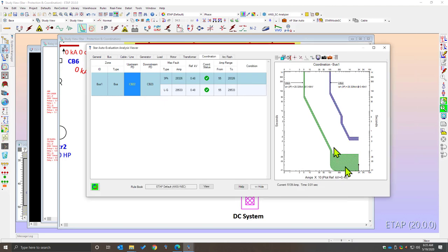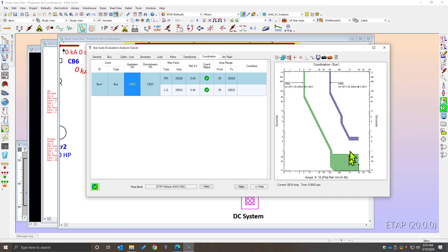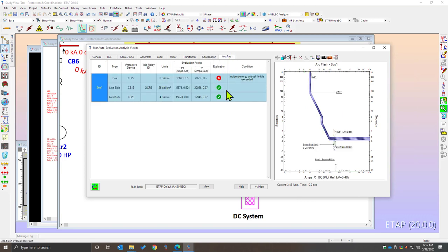You can simply expand the mini TCC, evaluate your protection settings, and choose the optimal setting for each case to automatically evaluate. By disabling the instantaneous, the program automatically does a coordination evaluation and gives you an updated view — we can see that bolted fault coordination now passes. Going to the Arc Flash page, we can now see that the Arc Flash incident energy is exceeding its critical limit, making this a balancing act that must be constantly iterated.